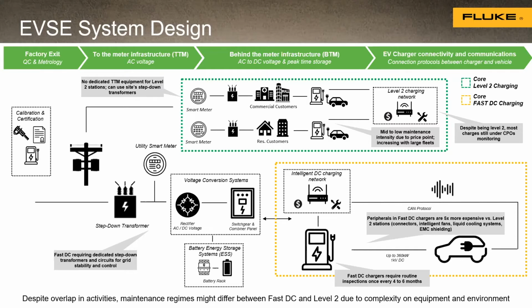The charging stations advance themselves. A level one charging station typically doesn't have fans in it—just some circuitry to change AC to DC and charge that station. Same with the level two type; even though voltages have increased, there's still not a lot of equipment inside. Once we get into these fast DC charge stations, there are fans and liquid cooling systems within them because they're pumping out an incredible amount of energy to try to charge these vehicles very rapidly.